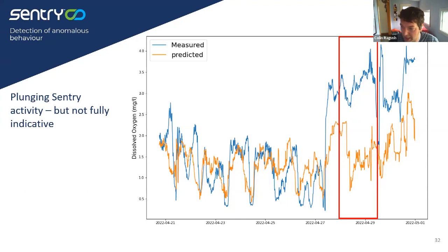Our model really begins to disagree about midday of the 27th, and it was about another day before you had actual problems come through in the measurements. So this highlights that models are more than just simply predictors. They're also great for understanding our processes and for seeing when process upset happens. And hopefully you can get out there a little bit sooner, collect the samples and determine the cause, both to protect the process, but also to learn so that problems don't happen again.